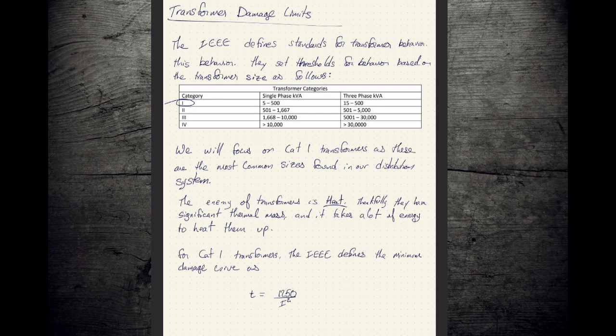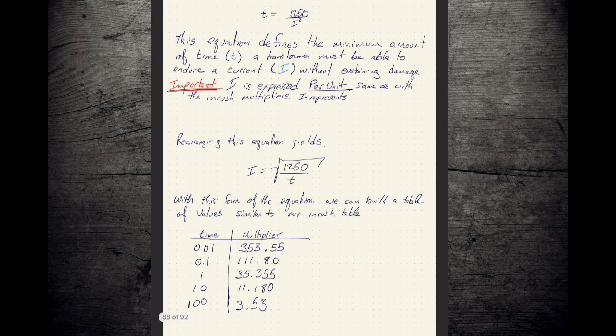So the fine folks at the IEEE, mostly being engineers and scientists, instead of going with empirical values for this, they decided we were going to use an equation. And the equation that they came up to is T equals 1250 over I squared. So here, T is time in seconds, and I is current per unit. Again, a multiplier of whatever transformer you're dealing with. Whatever its full load current rating is, this gets to be a multiplier value.